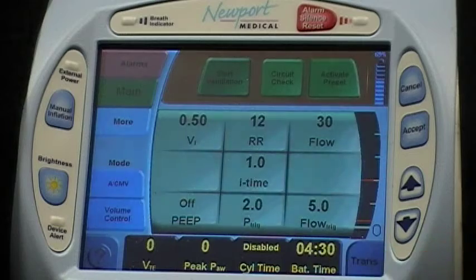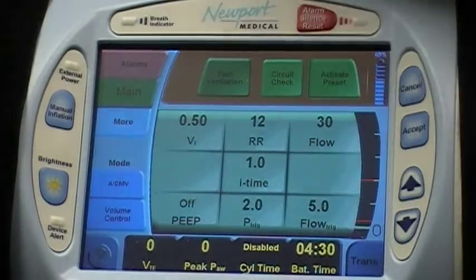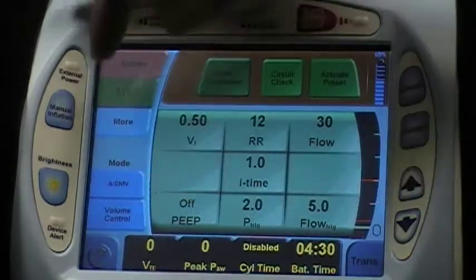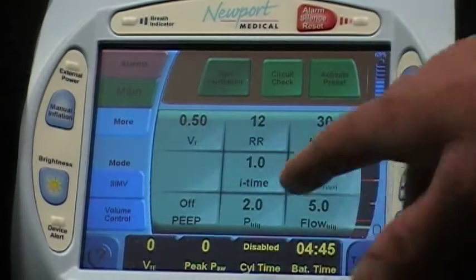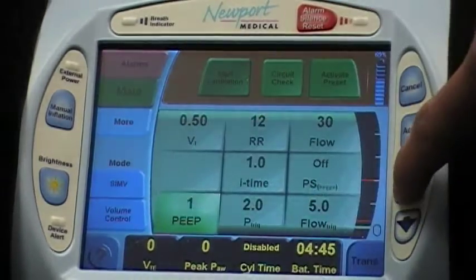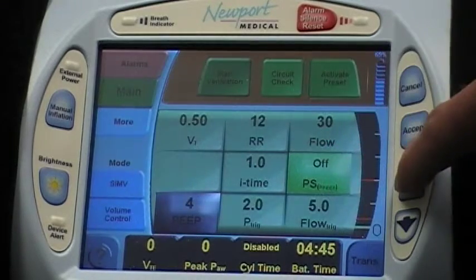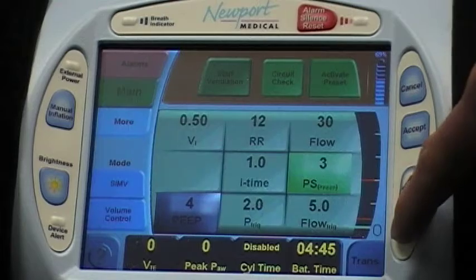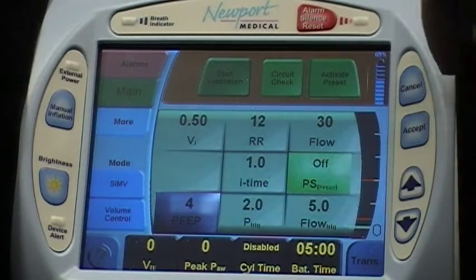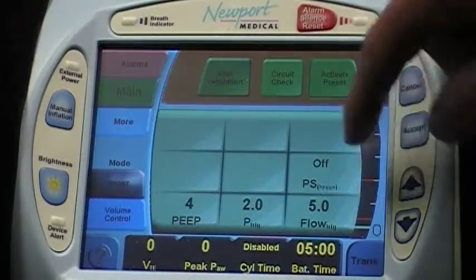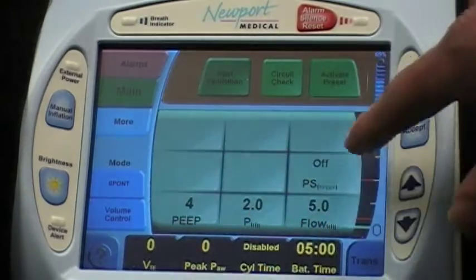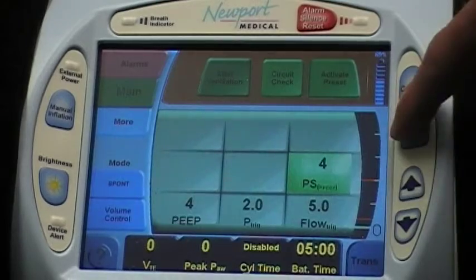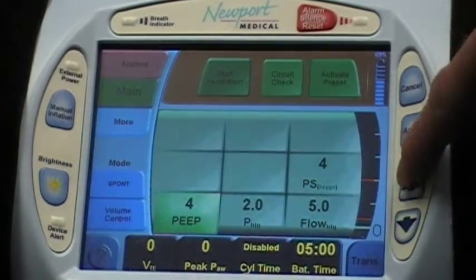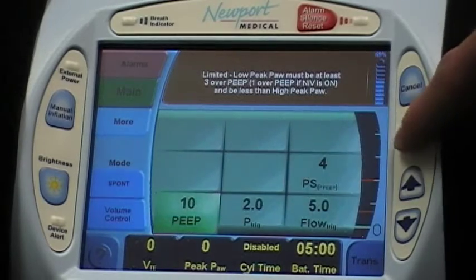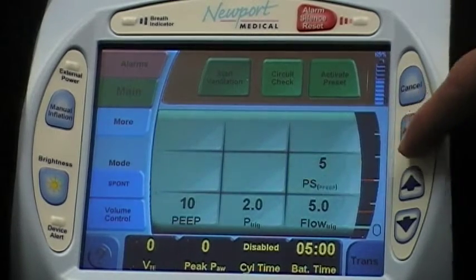On this vent, with my PEEP on, it'll give you CPAP. And I'll show you here. We're in SIMV. With my PEEP on, it'll give you CPAP. And if I add pressure support, that gives you BiPAP, in spontaneous mode. So PEEP gives you CPAP. When you add your pressure support, that gives you BiPAP. For instance, you could set your PEEP at 10, and you could set your pressure support at 5.